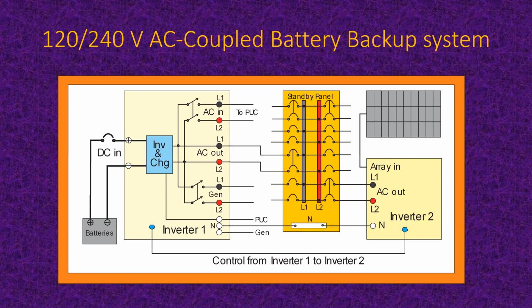Case number 3, no utility. In that case, that switch at the top there is going to open. That 2-pole switch at the AC in opens up because we have to disconnect from the utility, and that means any loads in the main distribution panel that might have been fed by solar previously are not going to be fed by it now. On the other hand, it's up to the solar to provide the energy for all of the needs of the loads in the standby panel. And it does that with the help of the batteries. So therefore, the solar comes on, makes AC electricity by way of inverter 2, powers the loads in the standby panel. Any leftover electricity goes to the inverter.